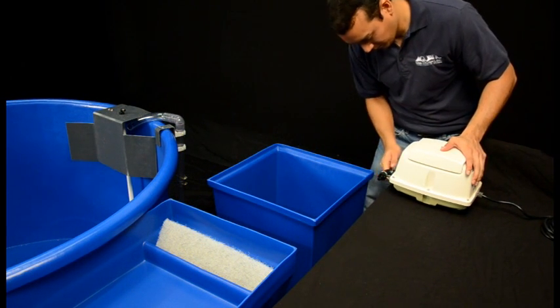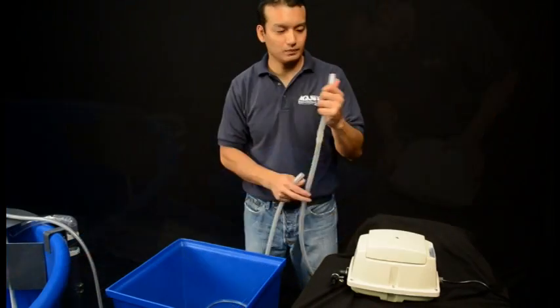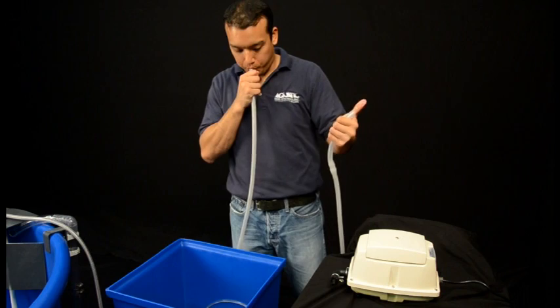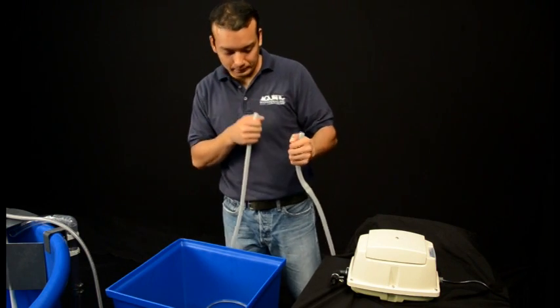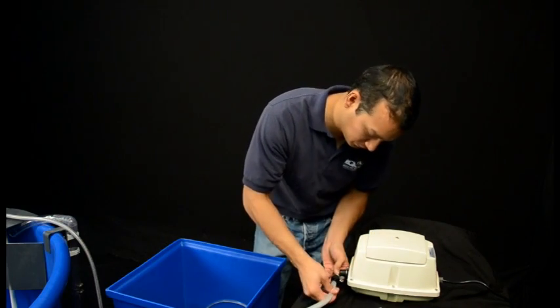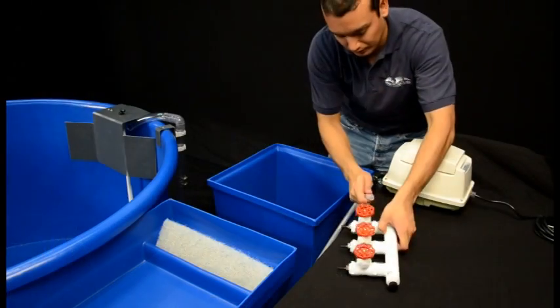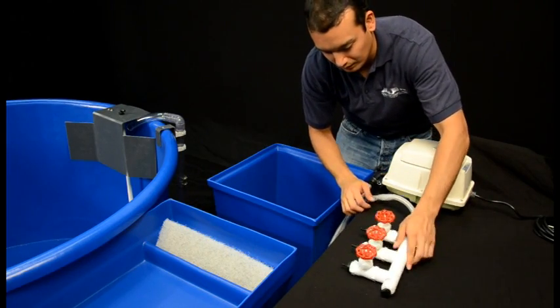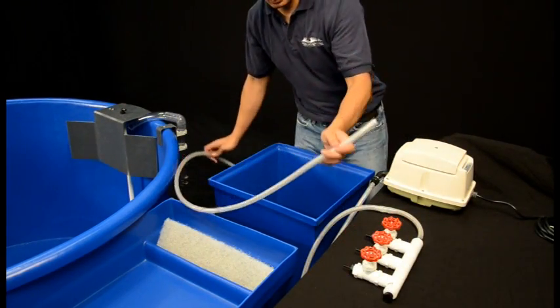To connect the air pump to the manifold, you will use the reinforced tubing run that contains a check valve. Test the check valve by blowing into each end of the tubing to determine which side is the inlet and which is the outlet. Connect the end of the tubing that allows airflow to the barb fitting on the air pump outlet. Connect the opposite end to the manifold inlet nipple.